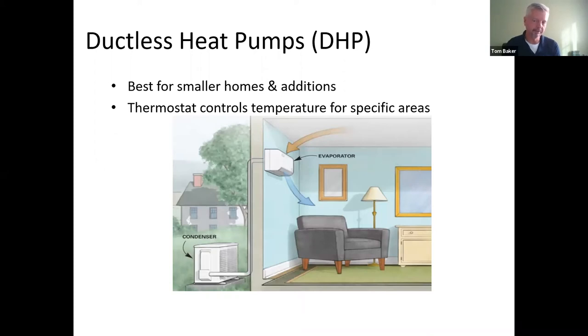So you can see in the picture here a good example of how it works. You've got your heat pump outside absorbing the heat. The refrigerant lines deliver that hot vapor to the coil inside. I don't know if you can see my mouse, but there's the cassette that sits up on the wall, and a fan in the cassette blows the air over the coil in the cassette directly into the room. So there's no duct loss in the ductless heat pumps like there would be in a standard heat pump, so you're getting even better efficiency out of it. The downside is if you were going to try to heat your whole home or cool your whole home with it, you'd need a cassette in each room or in each living space. So there are specific applications where this works really well, but it's not always the best solution for a whole home system.